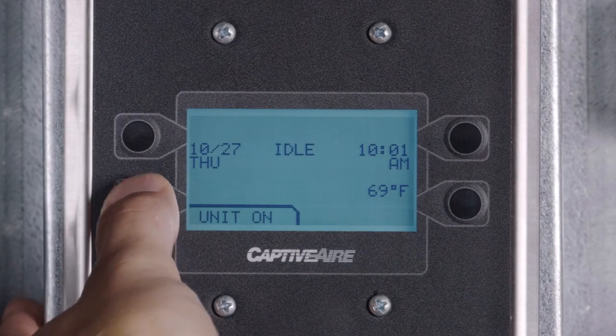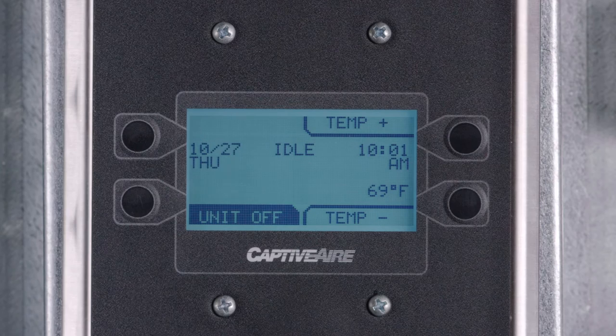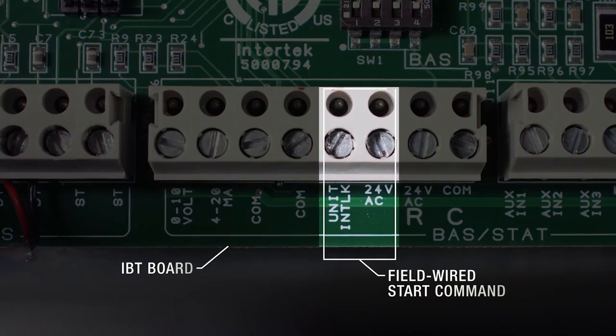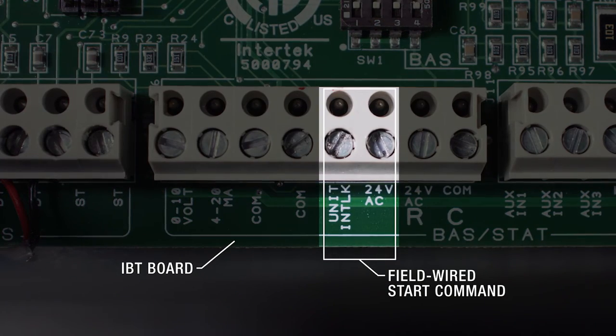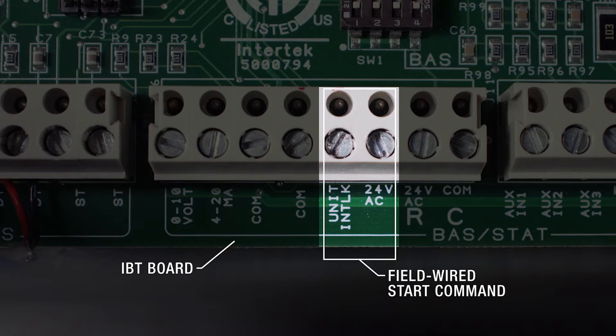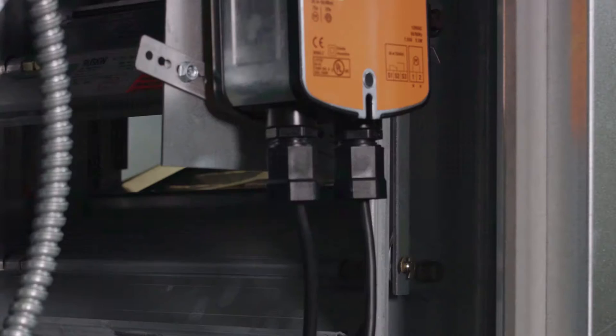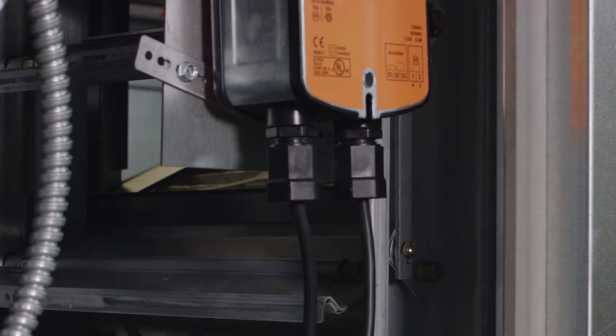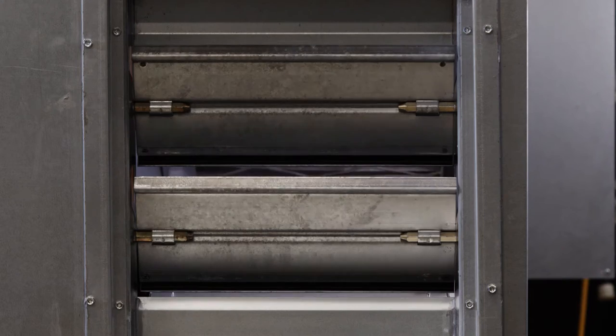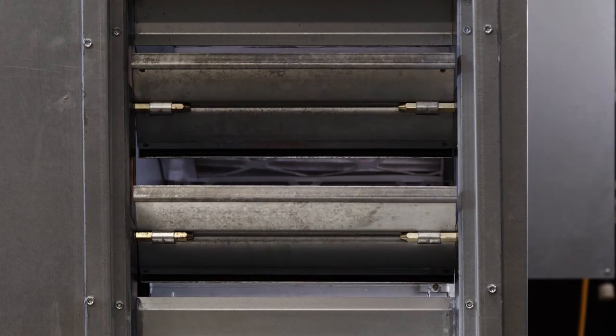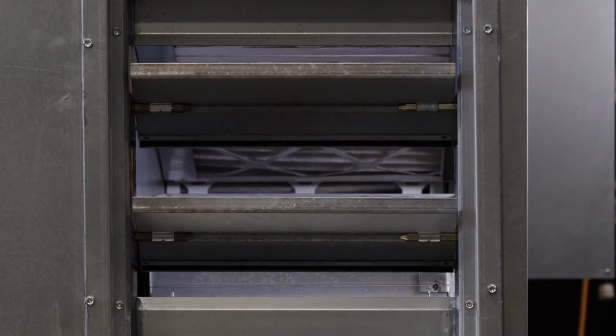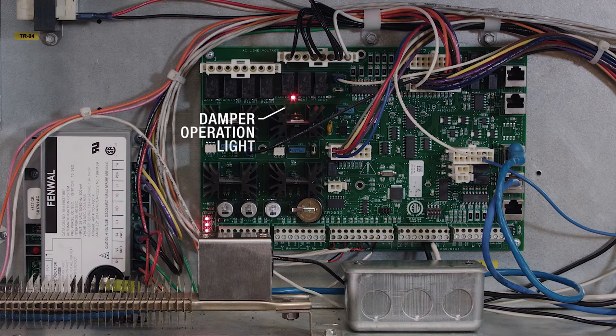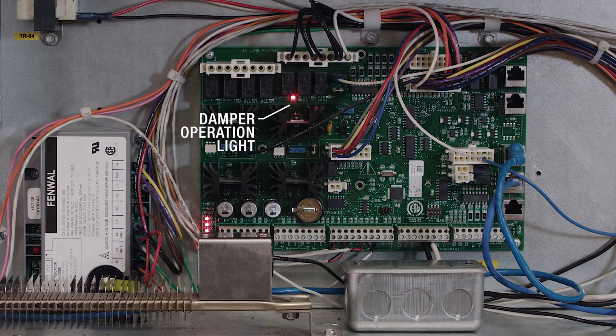Turn on the blower using the HMI as shown, or using the field wired start command. Note that if an intake damper is present, there will be a delay before the blower starts. The IBT board will display a red light while the damper is opening.